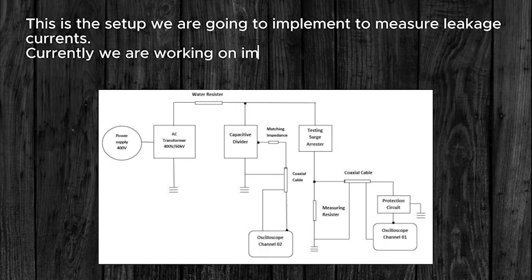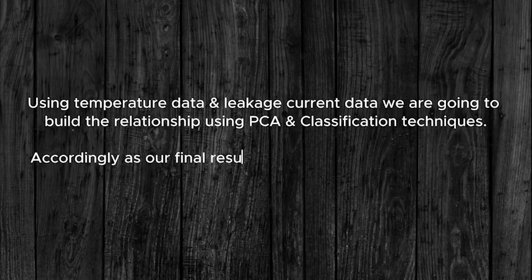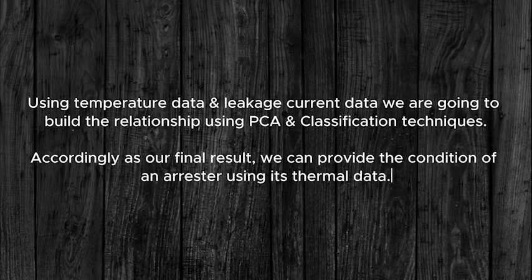This is the setup we are going to implement to measure leakage currents. We are currently working on implementing it in our high voltage laboratory. Using temperature data and leakage current data together, we will build a relationship using PCA and classification techniques. As our final result, we can provide the condition of an arrester using this thermal data.